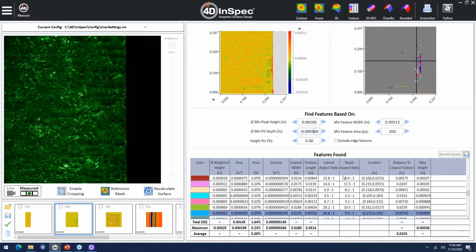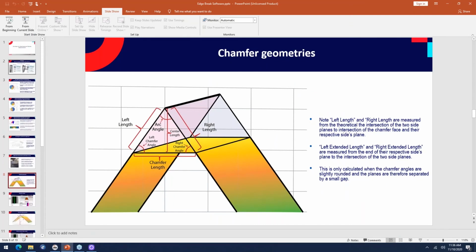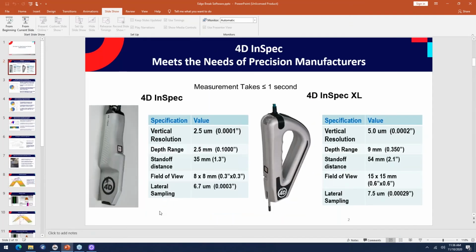Also, tied to what you're showing here, there is a question on lateral resolution. So basically, how small a feature would we be looking at? Yeah, the lateral resolution of the system is around 0.3 of a thou, or around 7 microns. Mathematically you would say twice that, but realistically, I would say anything smaller than a thou could be looked at laterally, or smaller than about 15 microns or so.